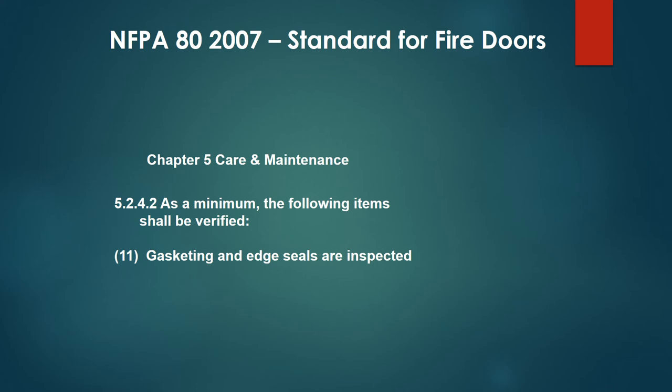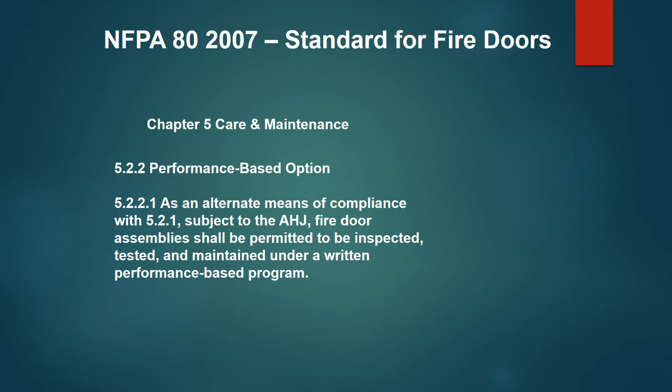Requirement number 11: gasketing and edge seals must be inspected. This comes down to knowing what type of doors you have and what edges, seals, and gaskets they require — whether it's intumescent material for fire doors or smoke gaskets for smoke doors. Knowing the differences is critical. There is an option to get relief from some of this maintenance through what's called a performance-based option.